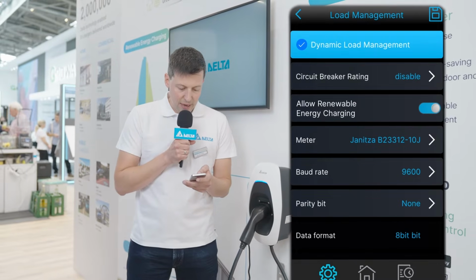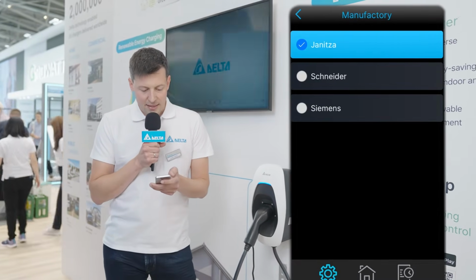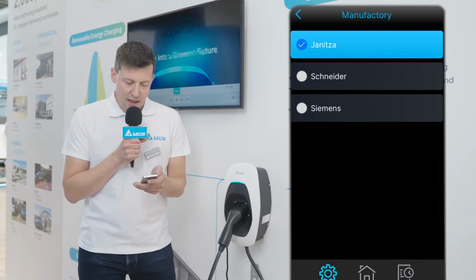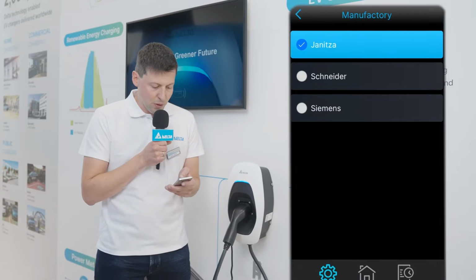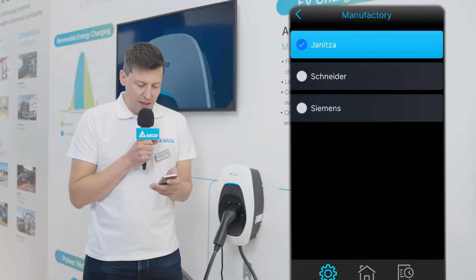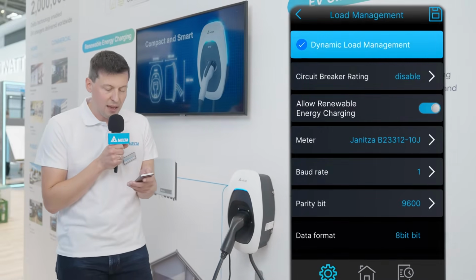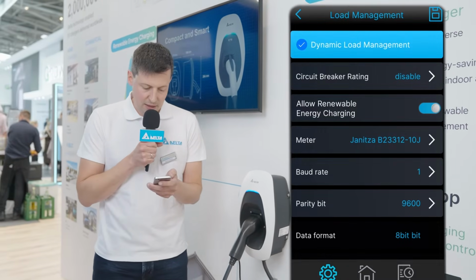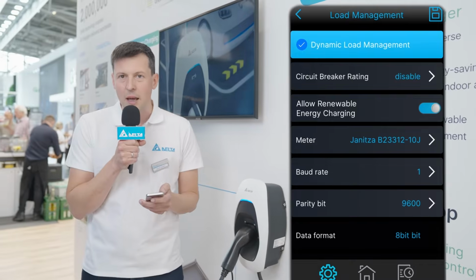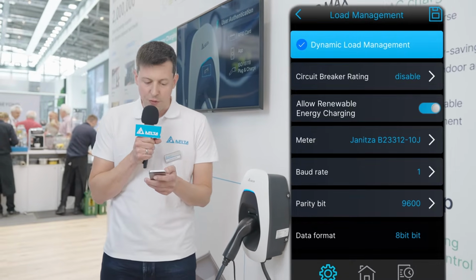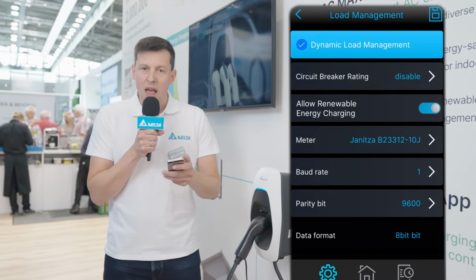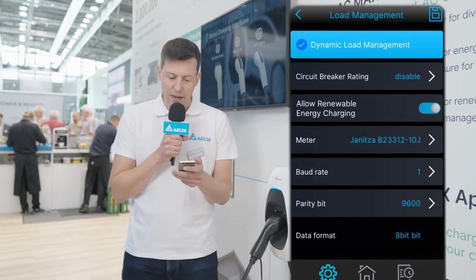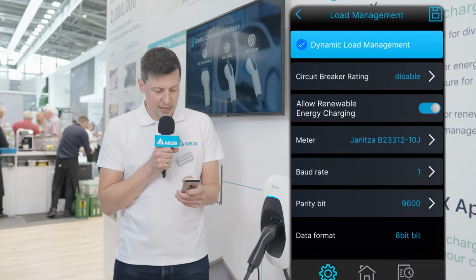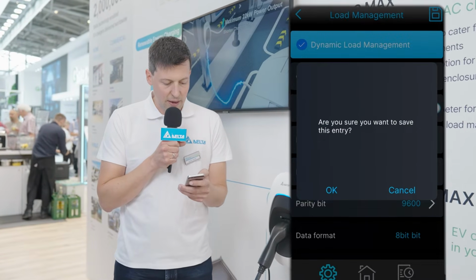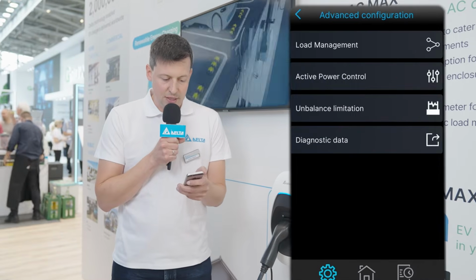We have pre-configured 3 energy meters for you: one from Janitza, one from Schneider, and one from Siemens. If you select one of those, the settings in the EV charger get pre-configured for communication with that meter - baud rate, parity bit, data bit information, everything. Once you select the meter used in your installation, AC Max gets completely configured accordingly. I can save the settings and go back to the main menu, and now everything is prepared to allow renewable energy charging.